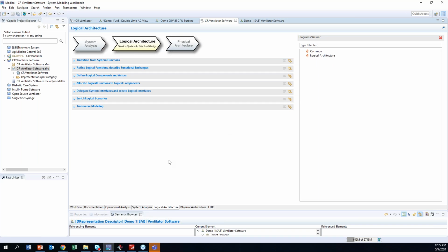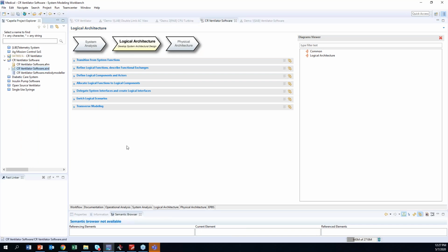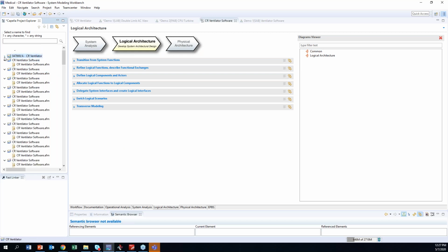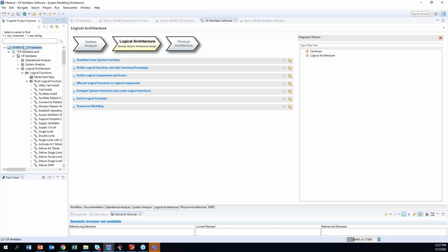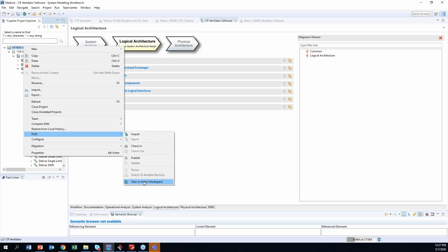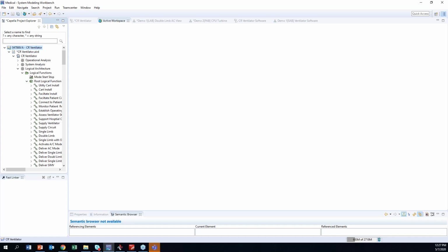No problem. So there's a question that said, in the context of 62304, is there any exporting functionality to some sort of document? How would you create a document to provide this communication with suppliers? Well, there's a couple ways. One way is that this information can be stored back into the PLM system. I'll show that here. And while I'm doing that, there's also a tool set that allows you to generate documents from the model. So we've got two options. We can generate documents from the model, and then those documents can be configuration controlled. It generates Word type documents.